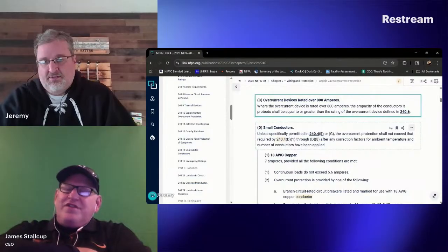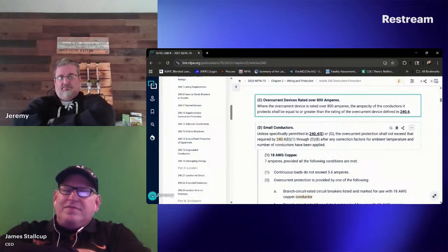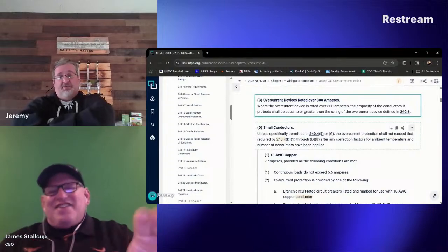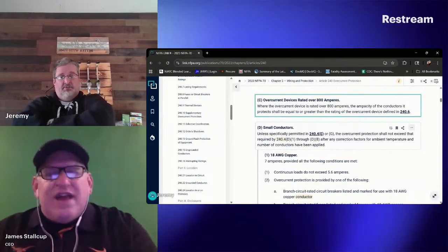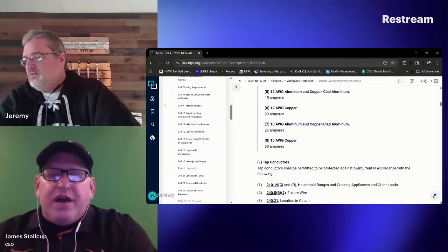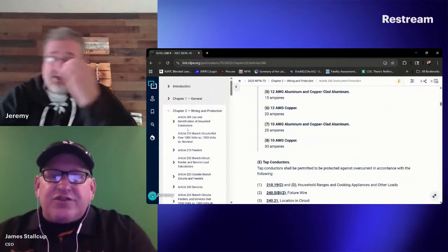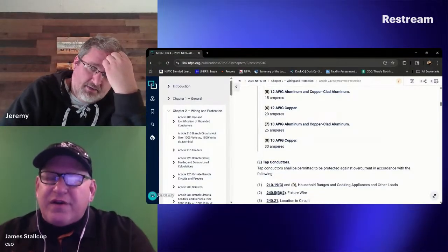Oh, well, that's interesting. So you're telling me that that service right there is going to be pulling 905 amps at all times? I never said that. I'm just saying what the code says. That's what I'm trying to tell you. That's what the code tells you to do. No, that's not what it's telling you to do. It's literally telling you that once you've already sized the conductors, they have to be equal to or greater than the rating of the overcurrent device.